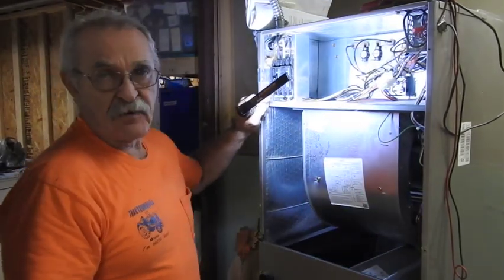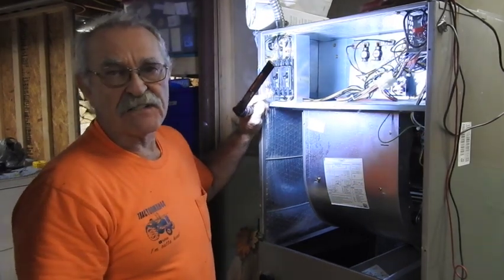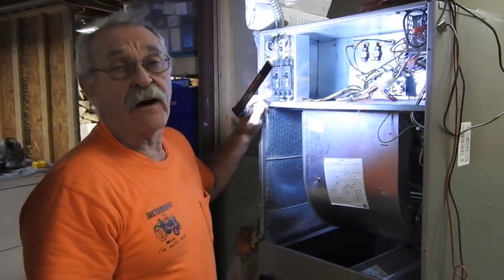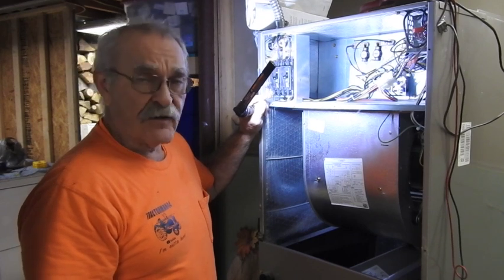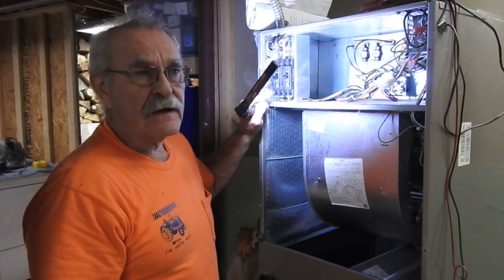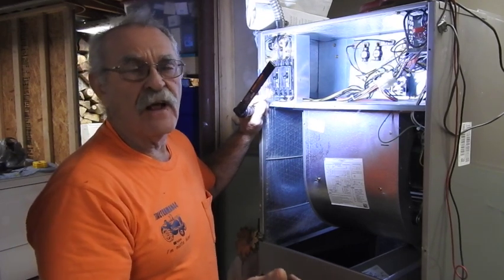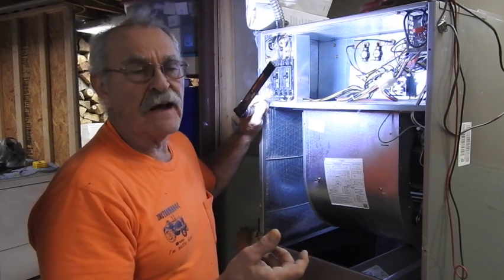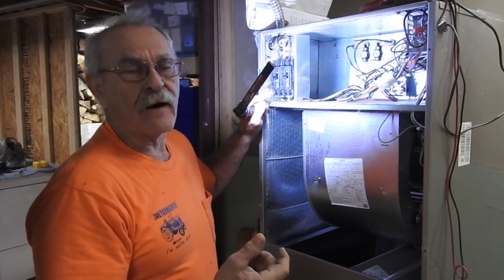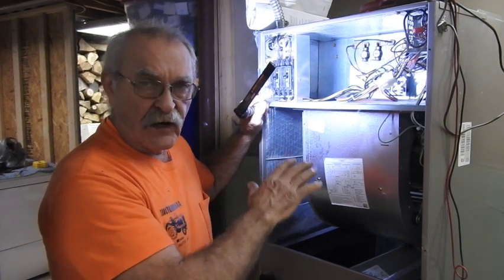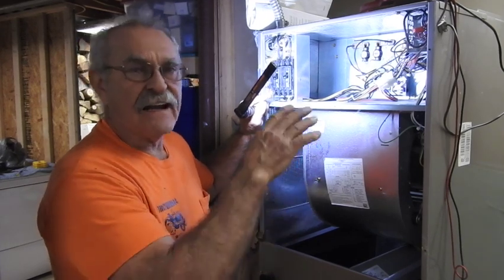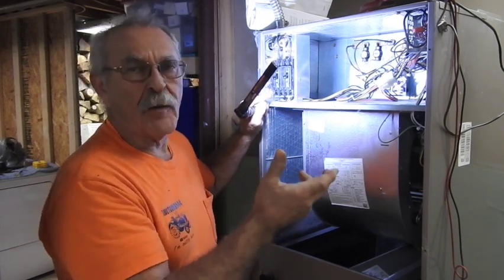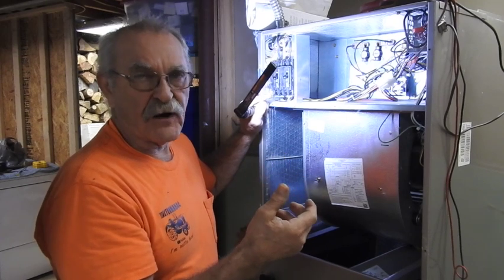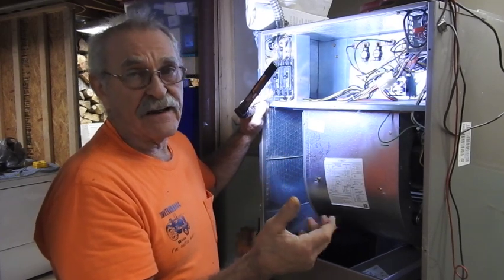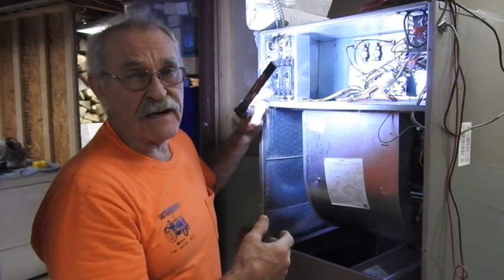And what happened with this thing here is, because this was such a grossly oversized air handler for the heat package, whenever the blower would come on, the temperature rise would be so low that it continuously blew cool air. It never ever blew warm air. You couldn't even get this low enough on the blower settings to have your temperature rise warm enough that it felt like heat was coming off of it. Now, there was definitely heat coming into the house. There was 53,000 BTUs of heat coming in the house.